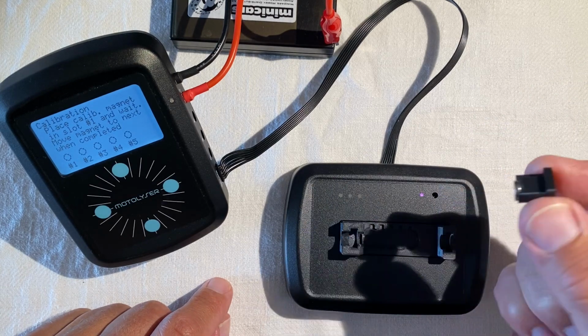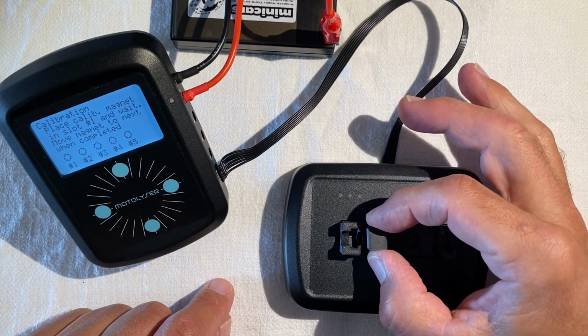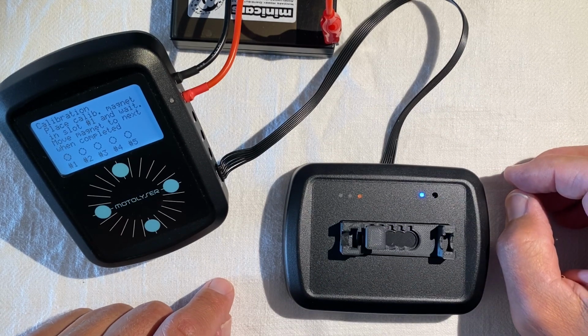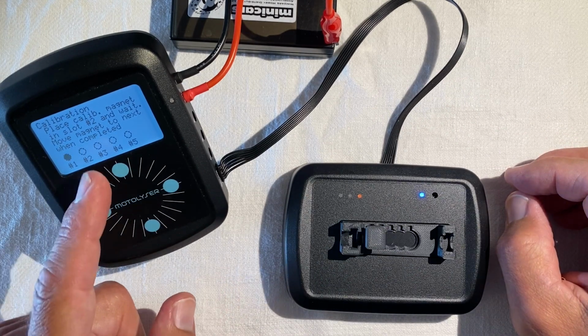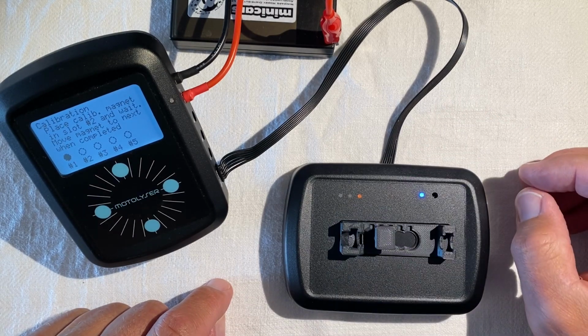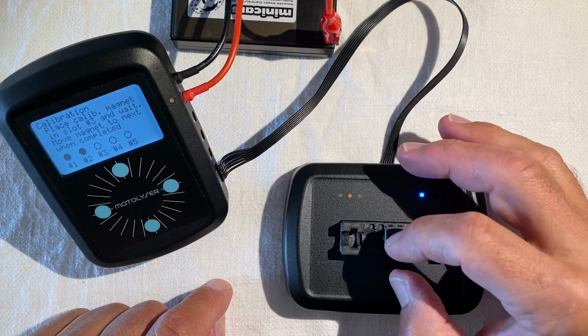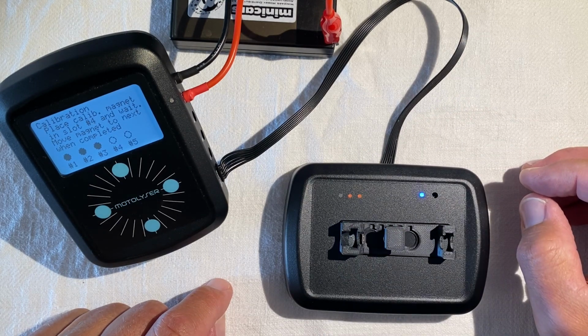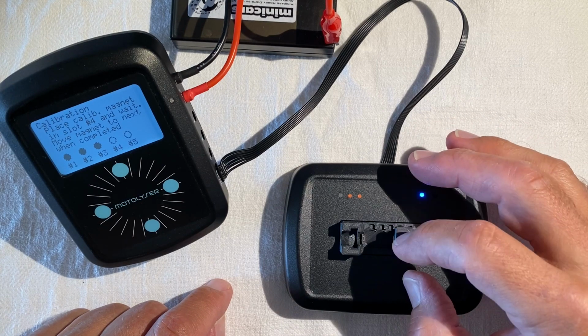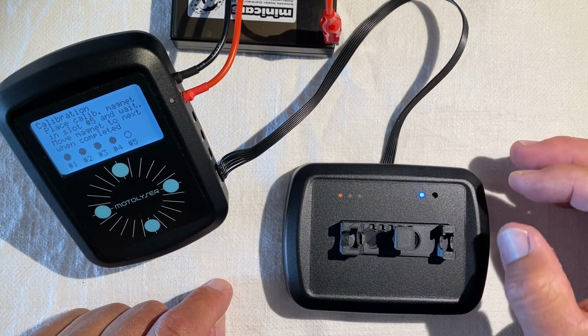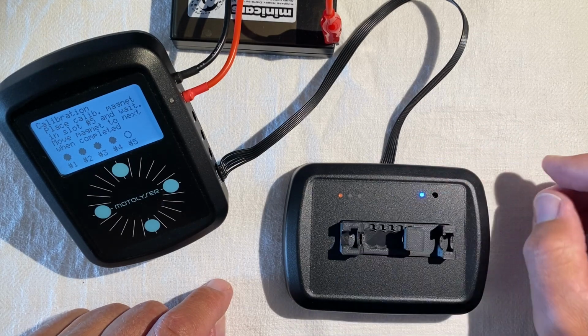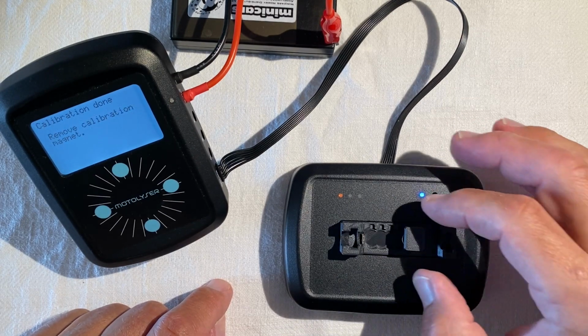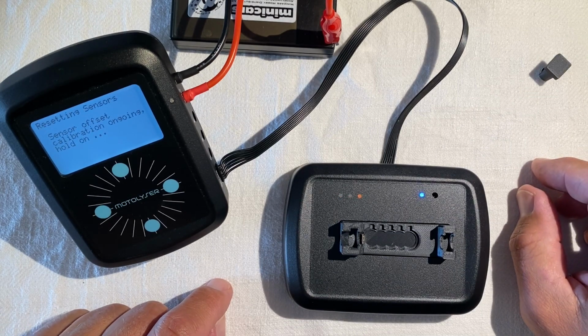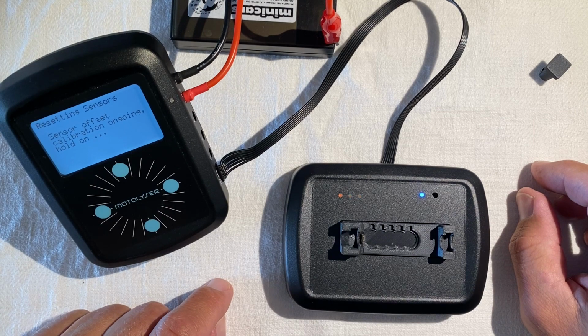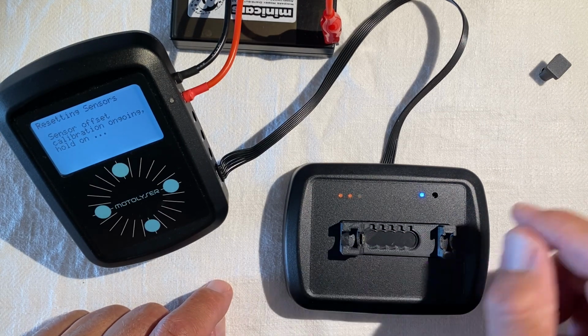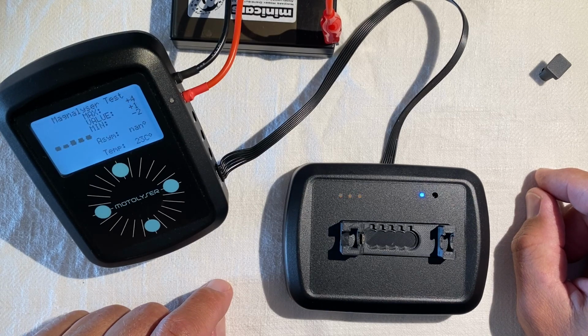You just take this calibration magnet that's provided with the kit, and you put it in the first slot and wait until it's done. And then it indicates it's done, and you move on to the next slot. And this is done throughout the 5 different sensors. You need to make sure it's thoroughly cleaned out, so you don't have any dust or anything, because that will offset the calibration and you will get inconsistent results. So when the calibration is completed, it goes back and just redoes the offset calibration.